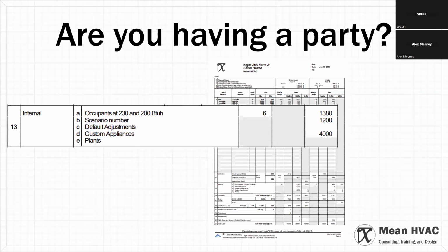So 1200 is the simple old-school scenario—I actually don't teach people to use that. 2000 to 2400 is scenario one, which accounts for not just kitchen appliances but some TVs and other electronic allowances for the home. Then there's scenario two, for situations with double refrigerators, an extra freezer, things like that, which runs around 3,400 BTUs. So that's my range—I'm looking for an appliance load somewhere between 1,000 and 3,000, or call it 3,500 BTUs, for a normal house.